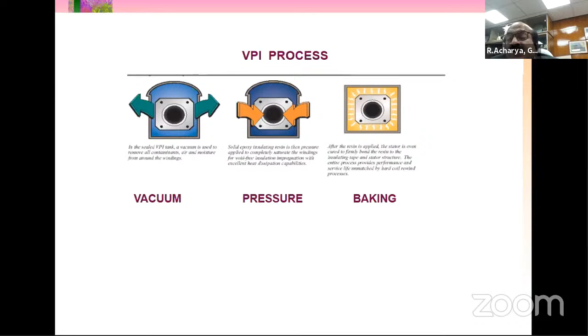VPI is not a very new process for the electrical industry. It has existed since the early 70s for smaller capacity applications. In fact, different kinds of impregnation processes, even our old fans, were fundamentally dip impregnation. But for large capacity machines, even up to 21 kV applications, machines are now available with total VPI impregnation, which is relatively new.